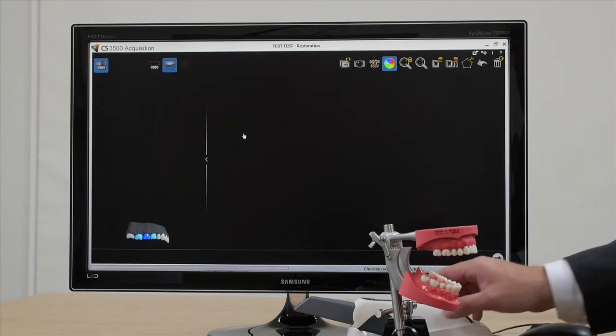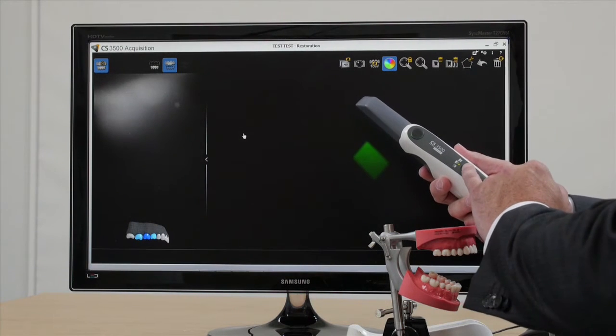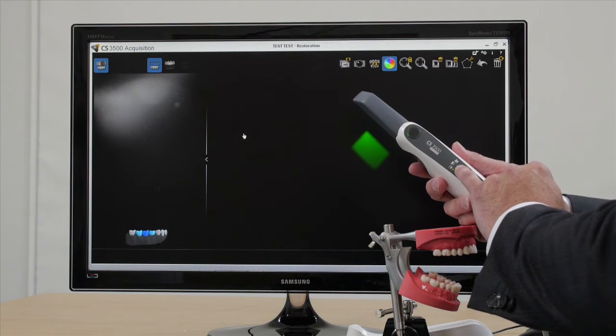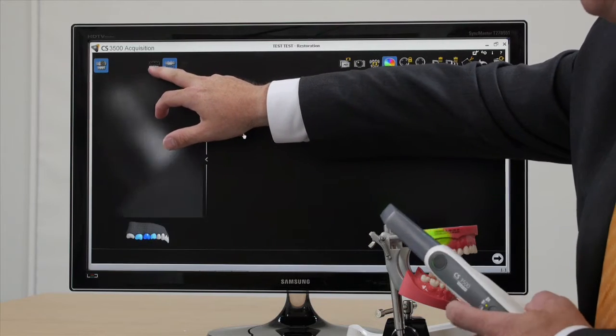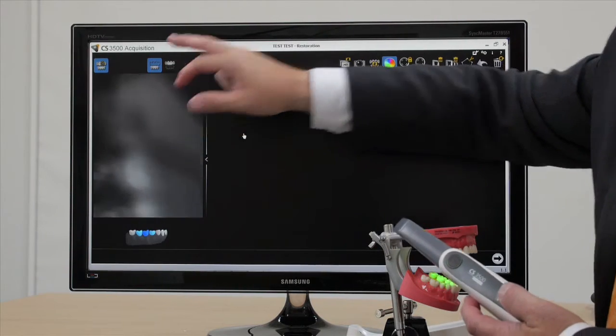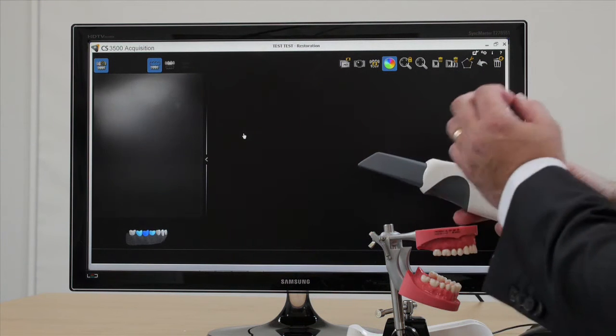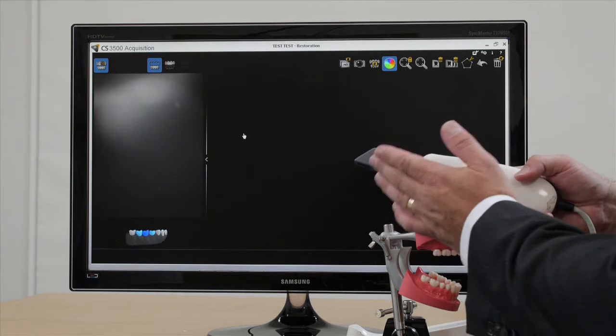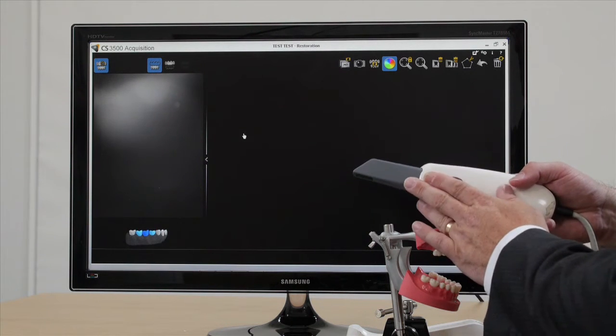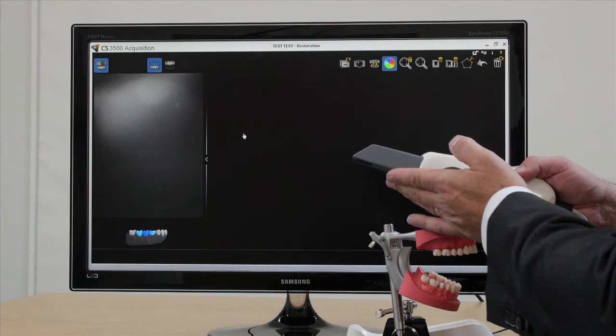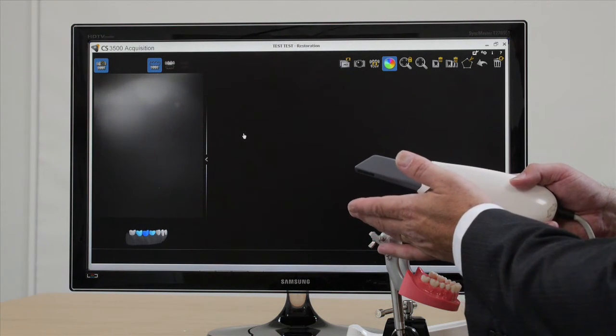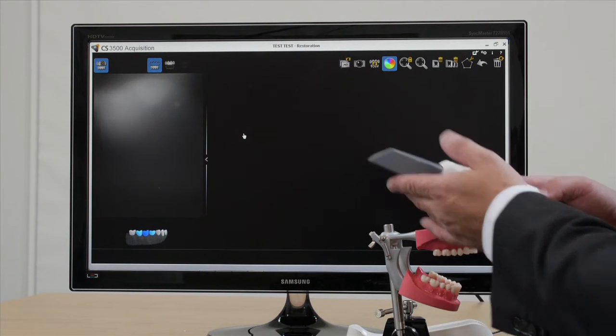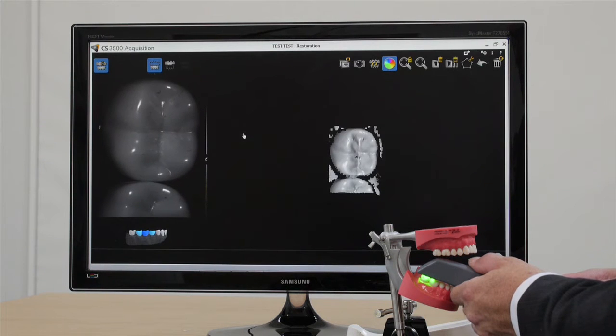Step two is are you starting to scan with the upper jaw or the lower jaw? It makes no difference to our system where you start. You can see here I've selected upper and now I've selected lower jaw. Our system is set to capture automatically images and the key trick or tip for scanning with this system is to rest this one tip on the occlusal surface of your teeth. So I'm going to start on the occlusal surface of the posterior teeth and I'm going to hold this scanner in position. There we go. There's my first picture.